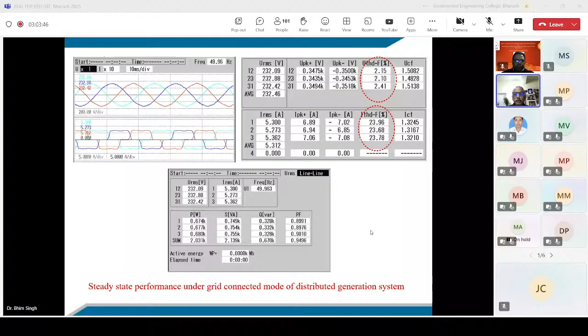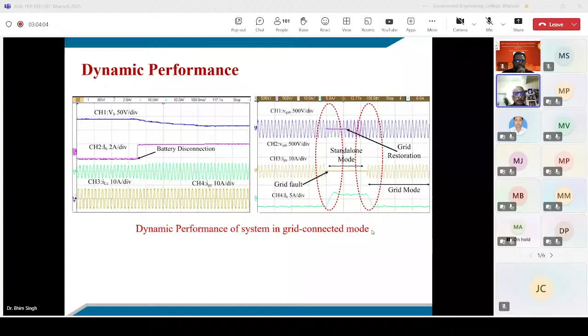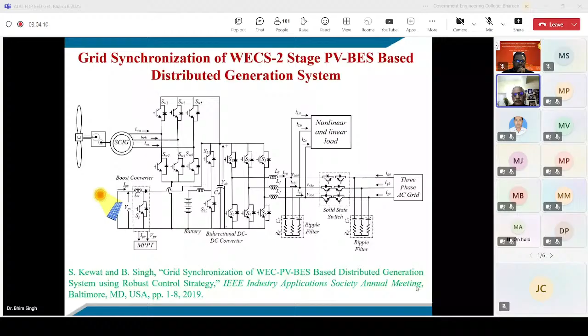Islanding happens because of grid fault or grid disturbance, and within 2-3 cycles we're able to reconnect back under different conditions. We extended this further to wind, solar and battery, and achieved synchronization with another kind of control working properly.